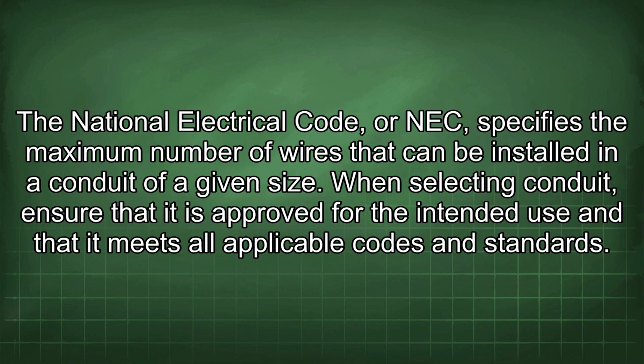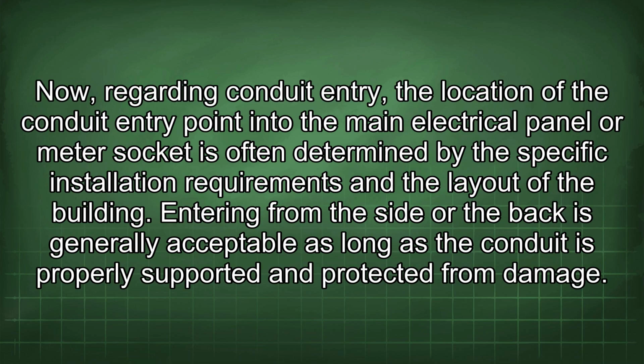The National Electrical Code, or NEC, specifies the maximum number of wires that can be installed in a conduit of a given size. When selecting conduit, ensure that it is approved for the intended use and that it meets all applicable codes and standards. Now, regarding conduit entry, the location of the conduit entry point into the main electrical panel or meter socket is often determined by the specific installation requirements and the layout of the building.